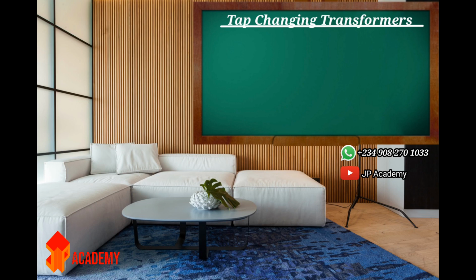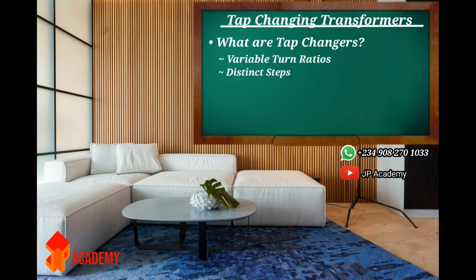Yes, I am teaching on tap changing transformers, but for the purpose of clarity, I would like to explain what a tap changer is. A tap changer is a mechanism embedded in transformers, which allows for variable turn ratios to be selected in distinct steps. This is done by connecting to a number of access points known as taps, which are along either the primary or secondary winding.